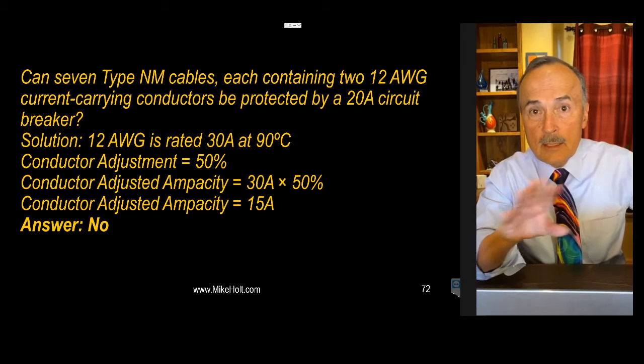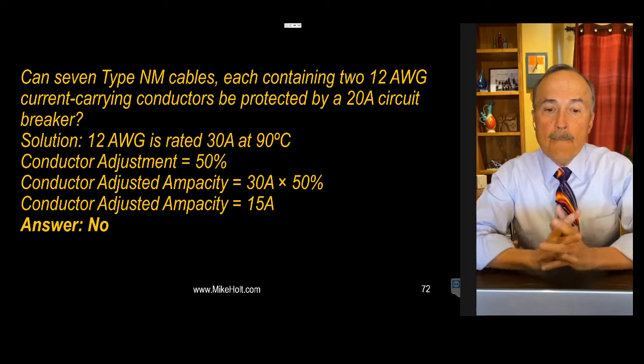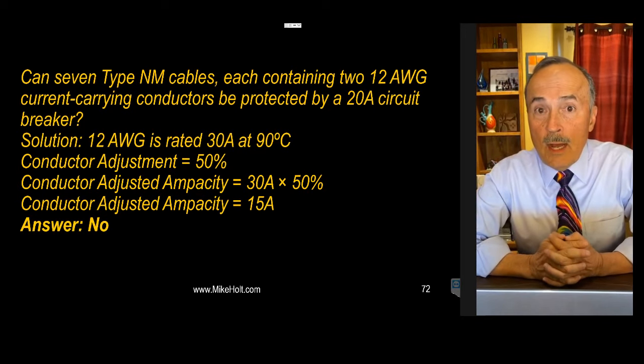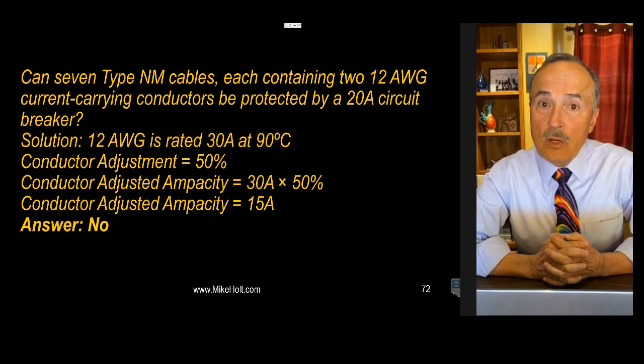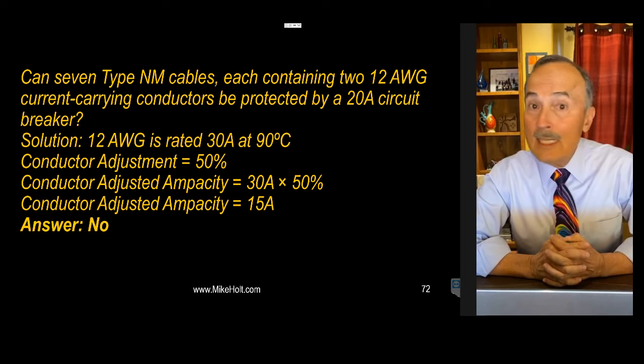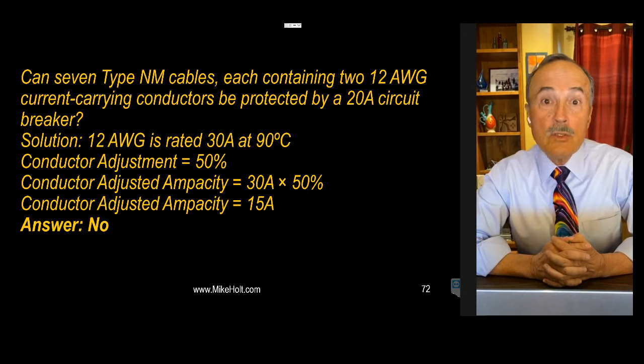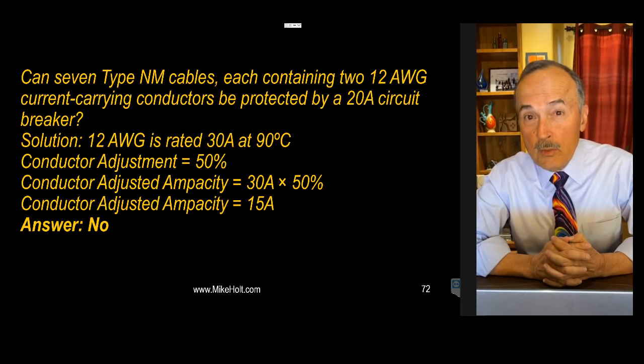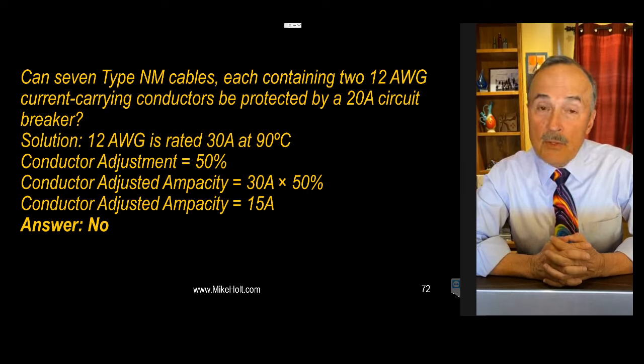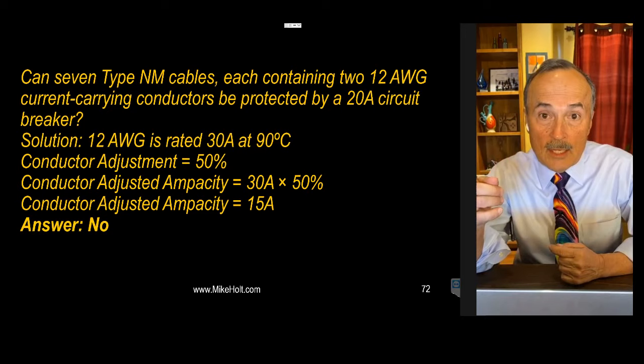And I mentioned that you go to table 310.16 in the code book, and you go to the 90°C column, always, anytime you adjust the ampacity of a conductor or correct the ampacity of a conductor, and that's another topic. We're not going to cover that now. So 12 gauge wire, a lot of electricians think that 12 gauge wire is rated for 20 amps. No, it is not rated for 20 amps. It's rated for 20 amps at certain temperatures, and it's rated for 30 amps at certain temperatures, depending upon what you're going to be doing with it.